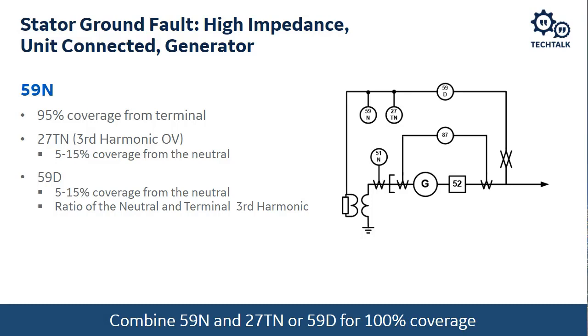So what do we do for that additional 5 to 10% coverage? What we could do is use a 27TN, which is an undervoltage third harmonic element, and we'll talk a little bit more about that on the following slides. Or we can also use a 59D, a 59 differential, which looks at the neutral voltage and the calculated zero sequence voltage from the terminal voltages of the transformer, and we do a differential between those two voltages. If there's an internal fault, then that differential will be non-zero, very similar to a current differential system.